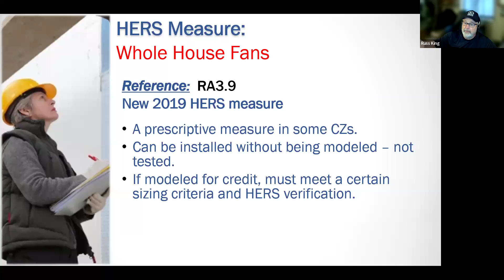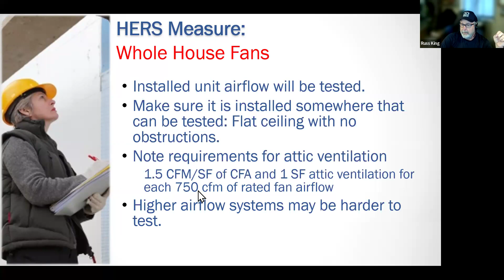Okay. I've seen whole house fans where they put the intake in the side of a skylight well. There is absolutely no way to test that. It's not a bad idea because it's pulling air through that skylight well, okay? But you can't test that. You cannot test it if it's only in a 2 foot wide space. There's no way to get the flow hood or any test device over the top of it. It can be very difficult to test that. So make sure it gets installed in a way that can be tested. Also, the whole house fan test triggers some requirements for attic ventilation. Okay, very important.